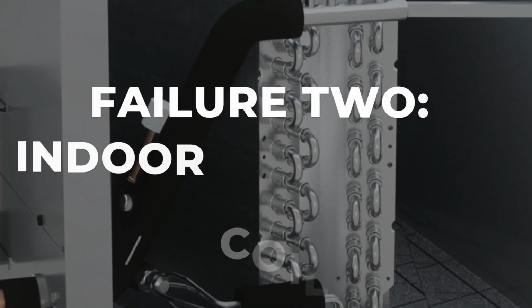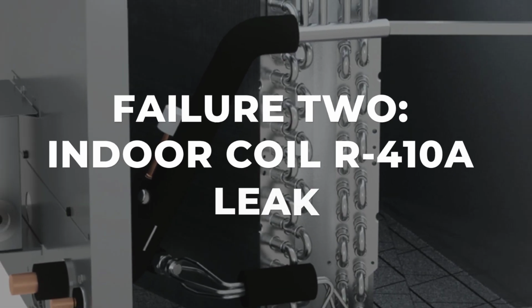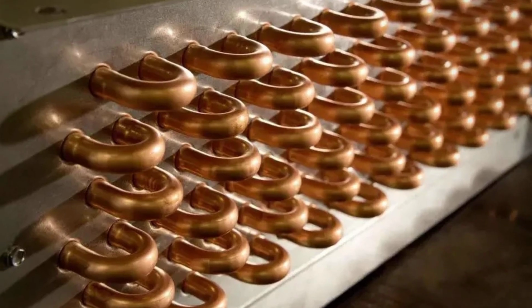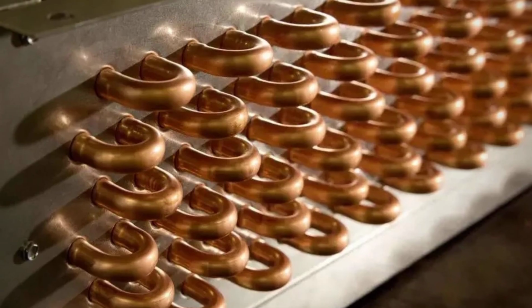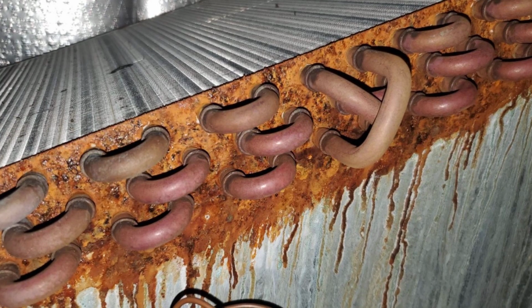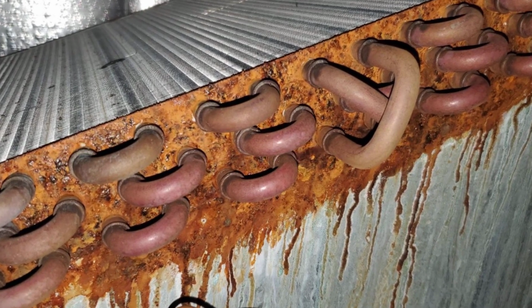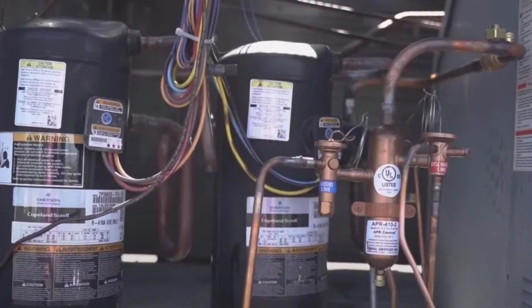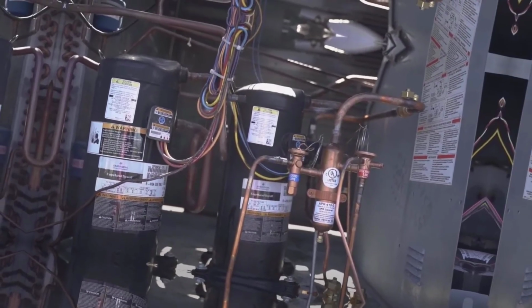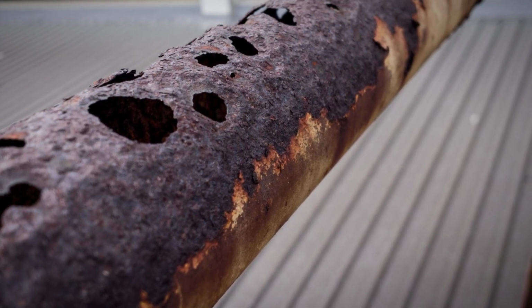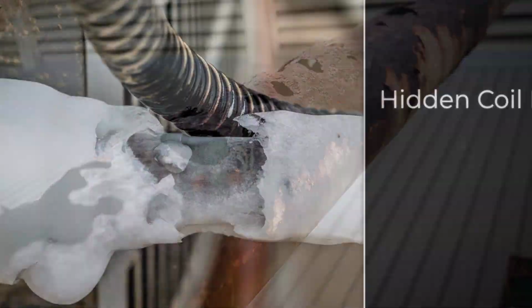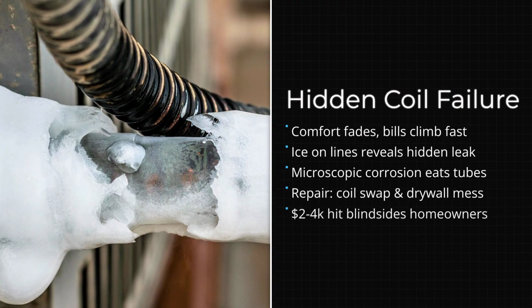Failure 2, the refrigerant leak in your indoor coil. Your evaporator, often still copper tubed in many split systems, develops a pinhole. Could be formicary corrosion from volatile organic compounds in your household air. Could be manufacturing contamination left in the lines. Could be thermal cycling fatigue on a tube wall that was spec'd for efficiency numbers, not longevity. You notice because the system stops cooling or heating properly, ice forms on the refrigerant lines, or the compressor starts short cycling every few minutes.